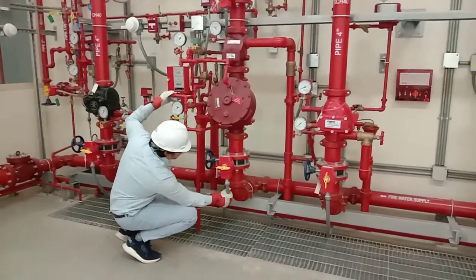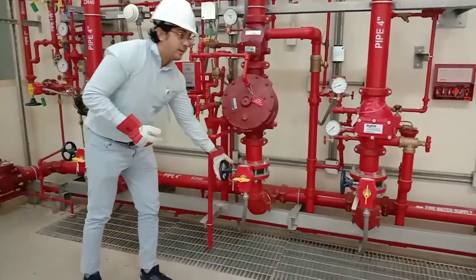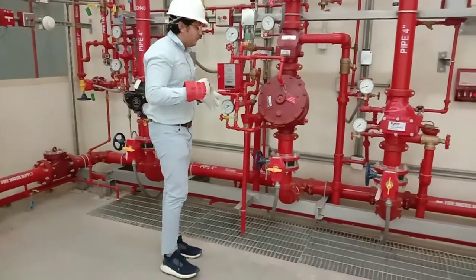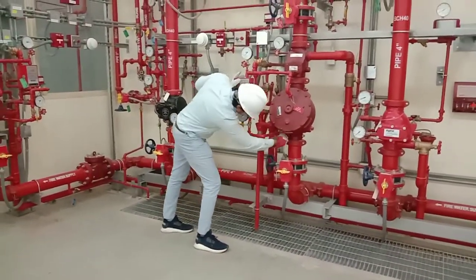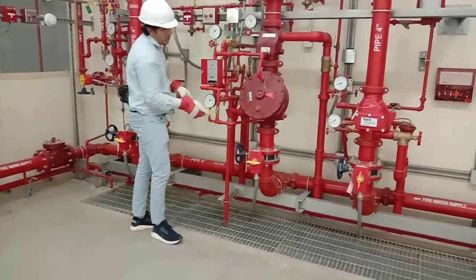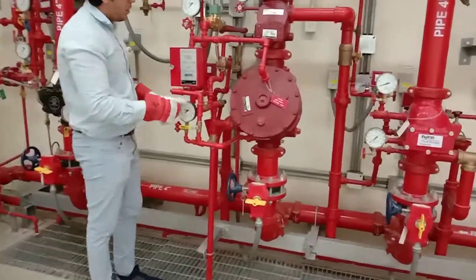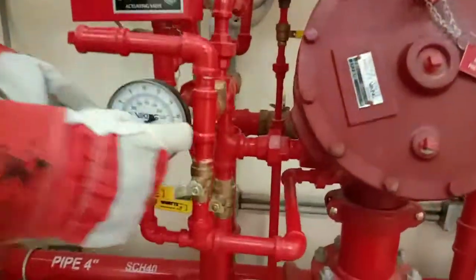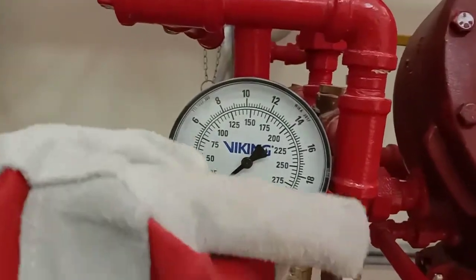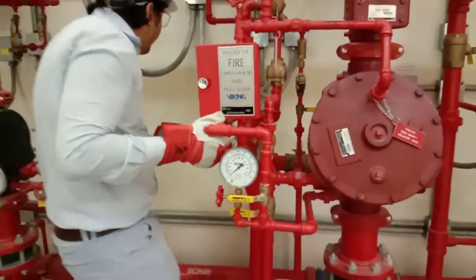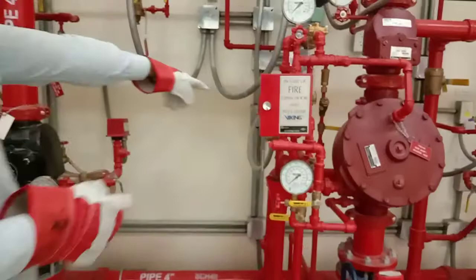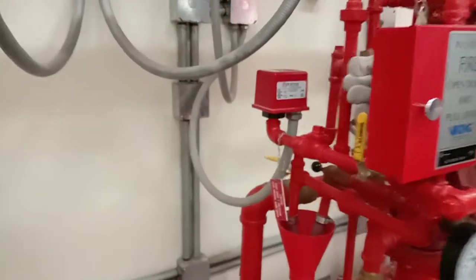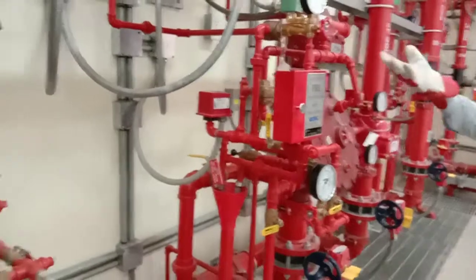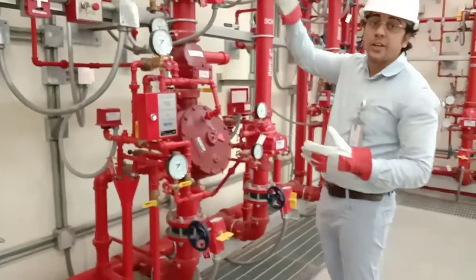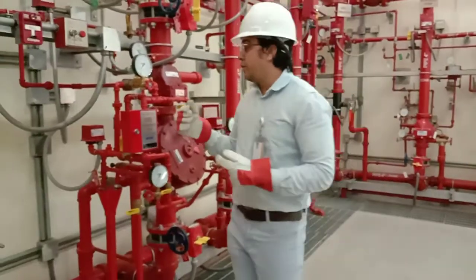The hard wire at the bottom, you can see, means it is supervised. If you try to open this wire outside, play with this one, it will give some signal to the fire alarm panel. Okay, now here we have a connection from the water supply line with this water gauge, right? So we can see what the inlet pressure is at the bottom of the valve. Here we can see the pressure, right? It's up to around 300 psi, and all the way from here, this line is connected with the pressure switch, right? So those pressure switches are PS10, it will give the pressure ratings, what the pressure is in the input. It is also supervised, so it will give a signal to the fire alarm panel in case the pressure is going high or going below the designed one. So this is for the water pressure.